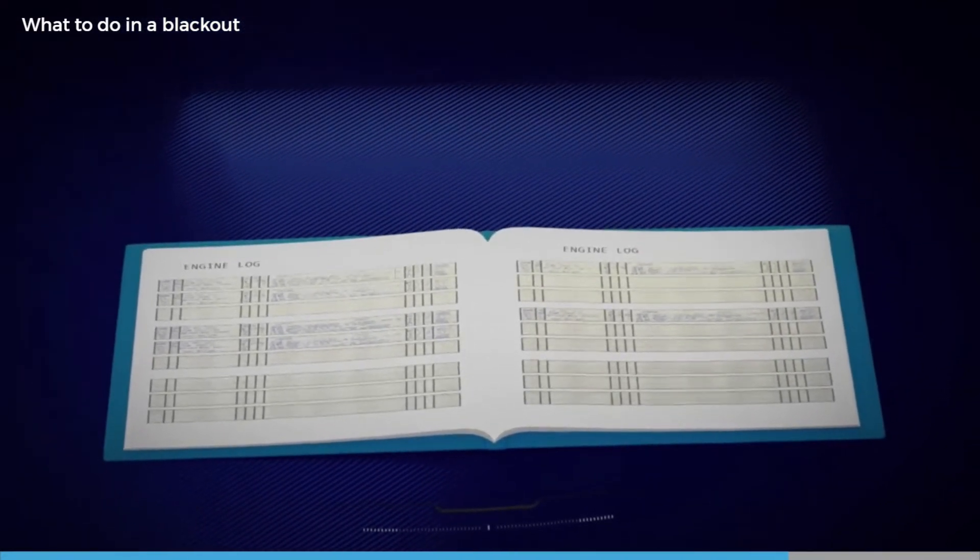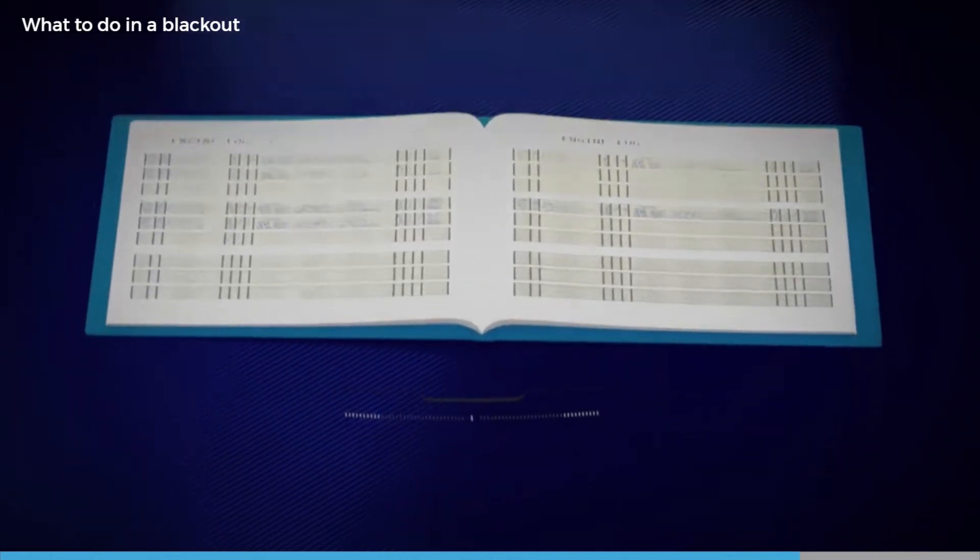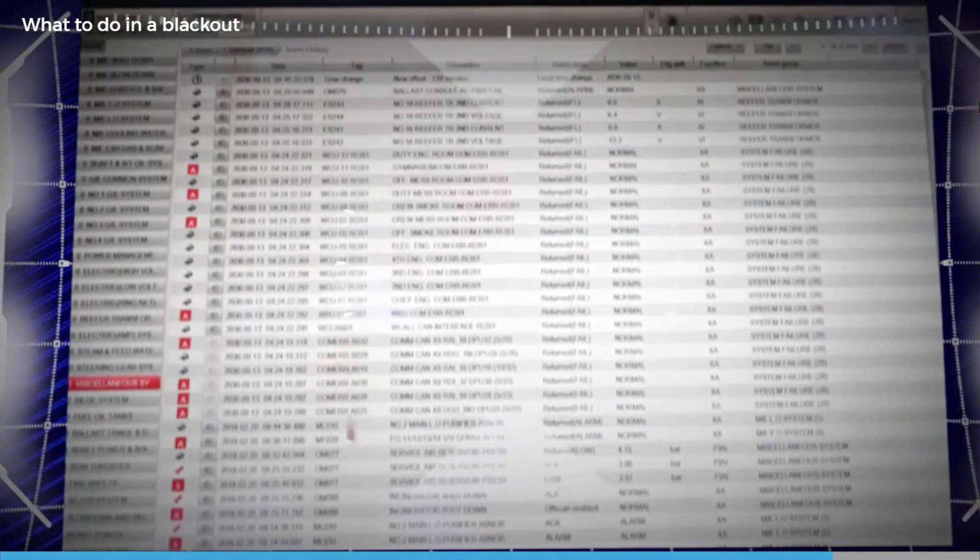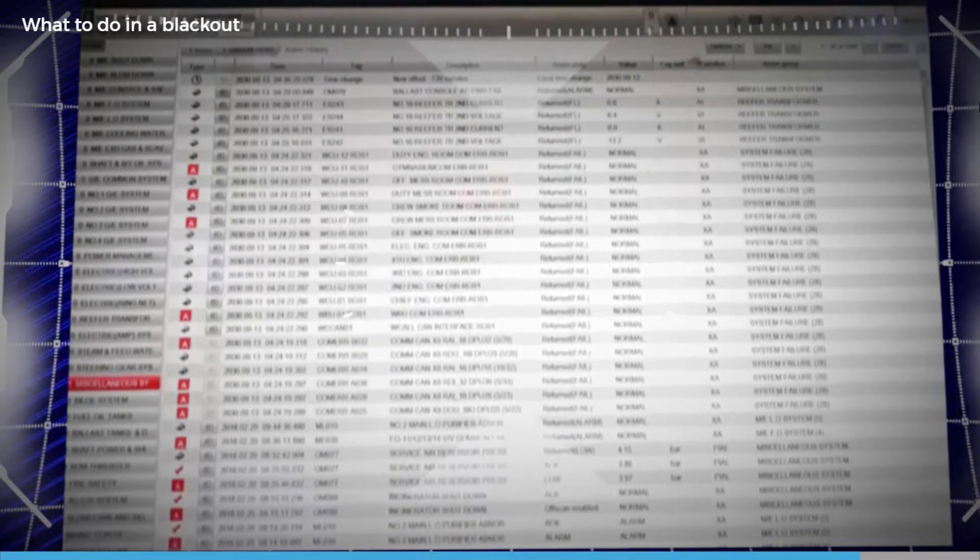Obviously, we should try and find out the reason for the blackout, and there might be some evidence of this in the data logger. Find out the reason for the blackout and fix it if you can, or isolate any defective equipment that caused the blackout.